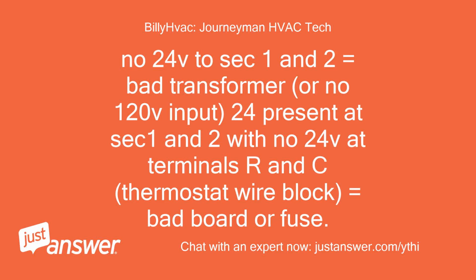No 24V to sec 1 and 2 equals bad transformer, or no 120V input. 24V present at sec 1 and 2 with no 24V at terminals R and C, thermostat wire block, equals bad board or fuse.